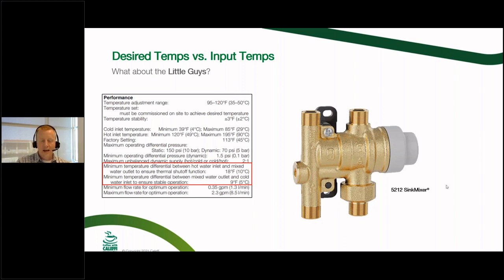So if you're setting this sink mixer to 110, and you want that thermal shutoff function to still work, you need to have roughly 128 degrees coming into that guy. And again, this is not just a Caleffi mixing valve thing, this is everybody's mixing valve thing. It's something you want to watch out for. There are also some requirements between cold water inlet and mixed water outlet desired temperatures that you want to maintain a differential on as well, because again, it's working with what it's got, and if the cold water inlet's too warm, it can't cool the water down. So make sure you're abiding by these, because these are the reasons why people call us up and say, I don't think this thing is working properly. It's not the mixing valve's fault, it's just a product of its environment, and it's something we've got to avoid.